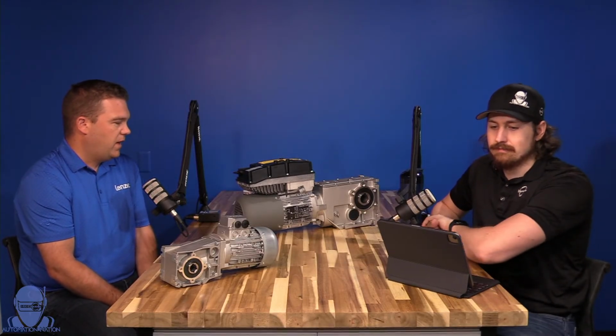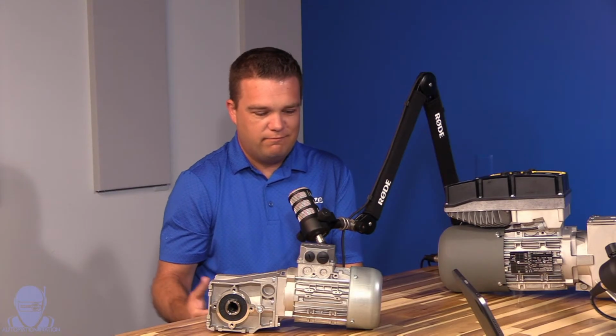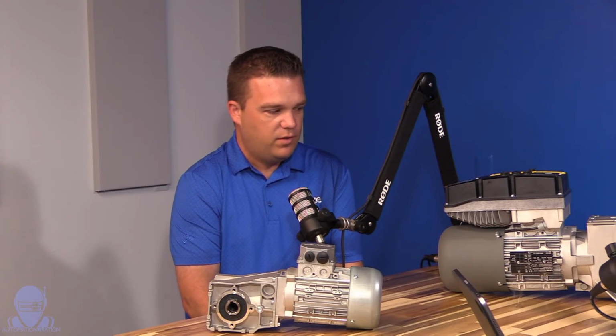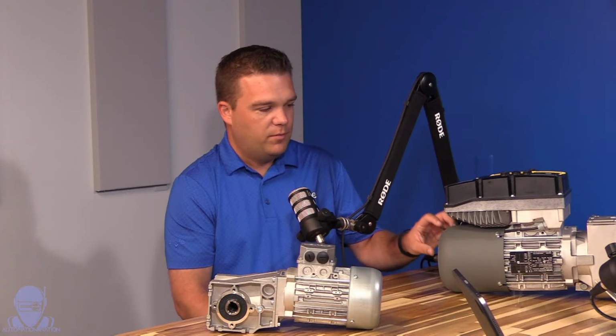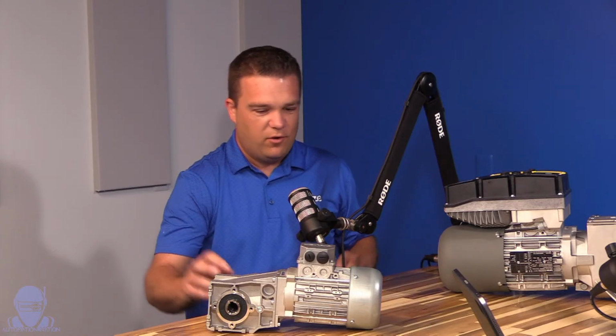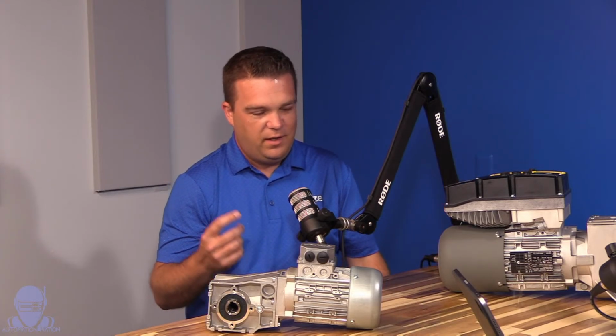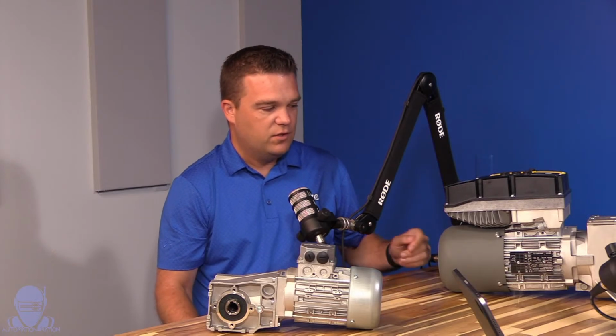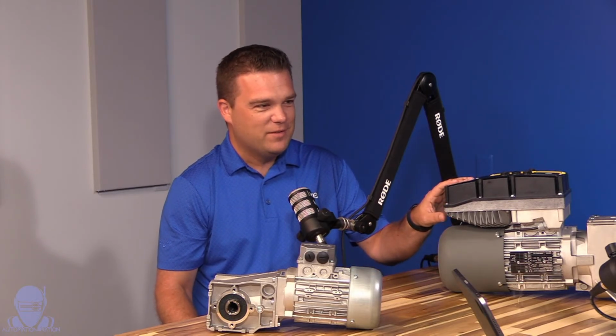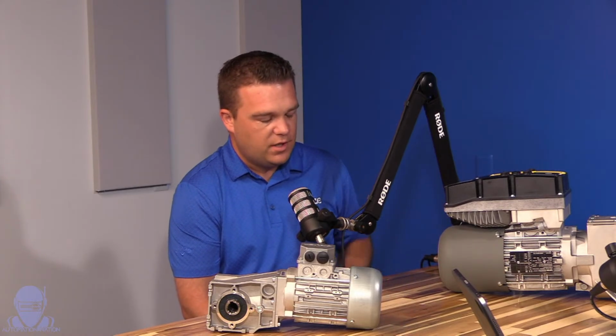Yeah, I think we're trying to provide a solution, right? The industry is getting smarter. People are getting smarter. Total cost of ownership is becoming a big thing as opposed to just cost of components. When you look at a gearbox with a motor with a VFD mounted to it, compared to a gearbox and a motor and a cabinet-mount VFD, this component may be more expensive. But when you start to look at eliminating or minimizing a cabinet size, and reducing the length of your expensive cables coming from a VFD panel, especially in bigger distribution centers, it provides a significant benefit to the industry.